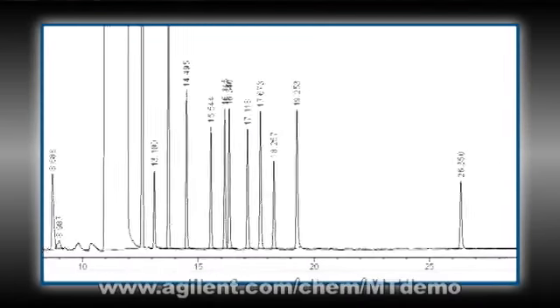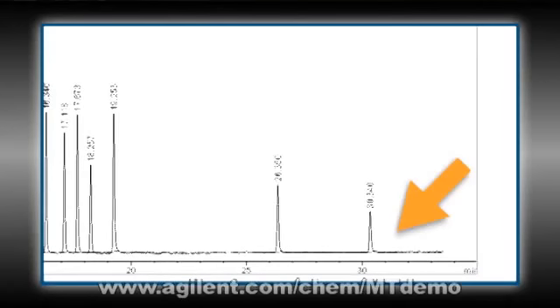They're doing 20 impurities in cumene. And right away, you can see there's a lot of run time at the end that seems to be a waste of time. Overall, it's a 30-minute run where we're waiting 10 minutes for the last two peaks, basically. There's a lot of things we can do here.